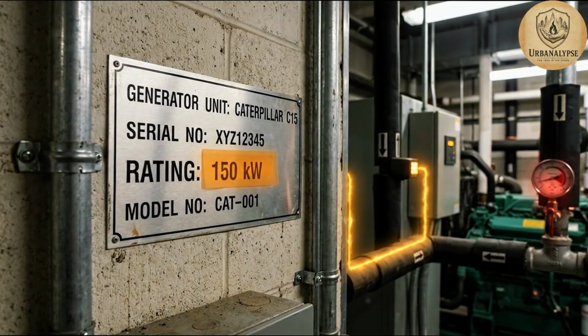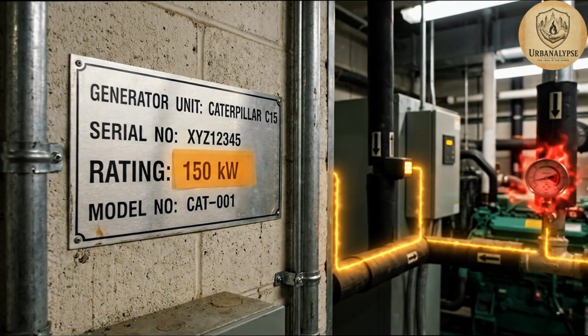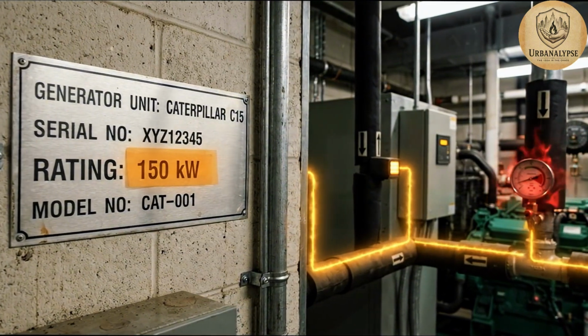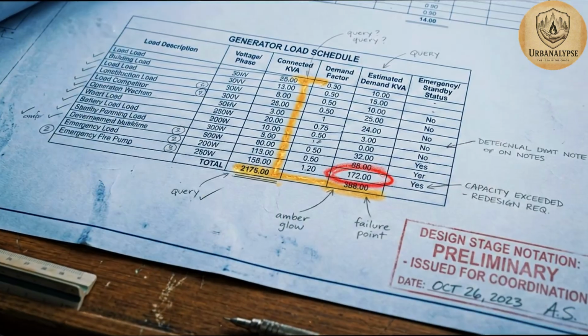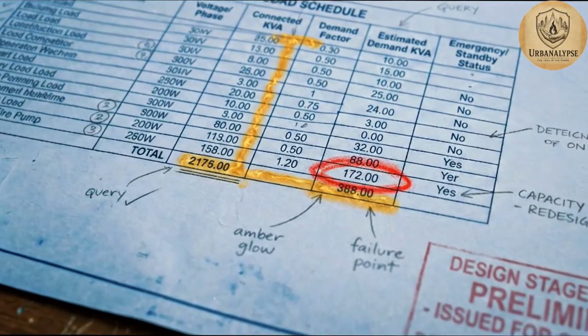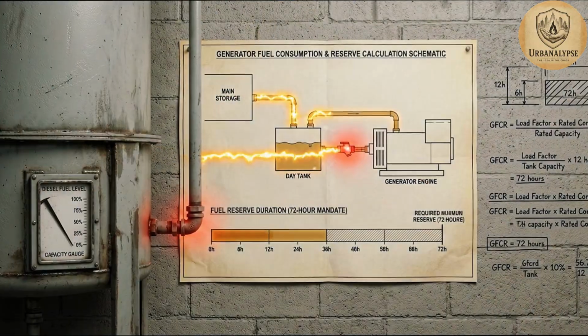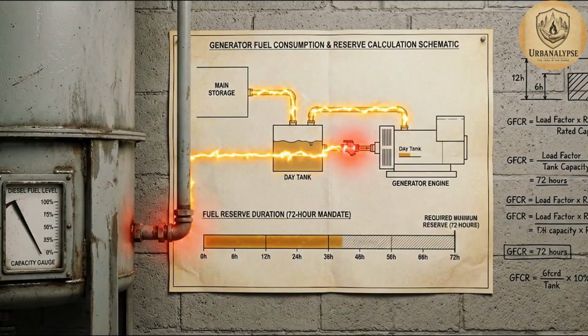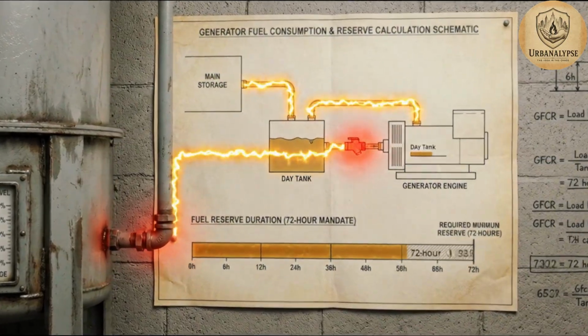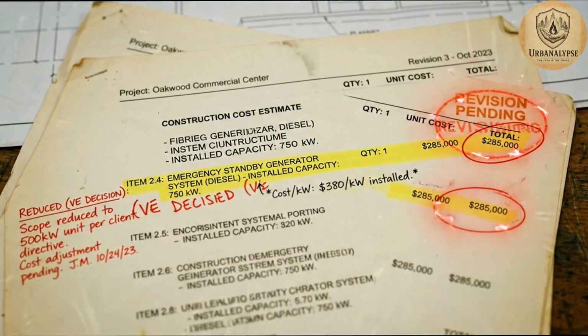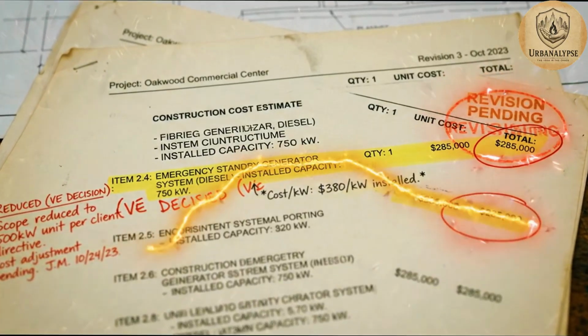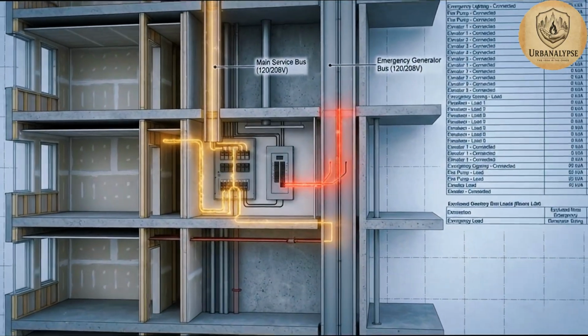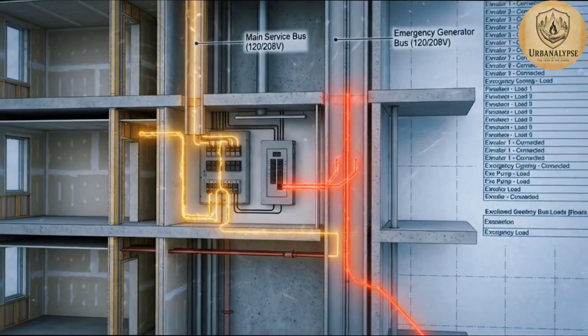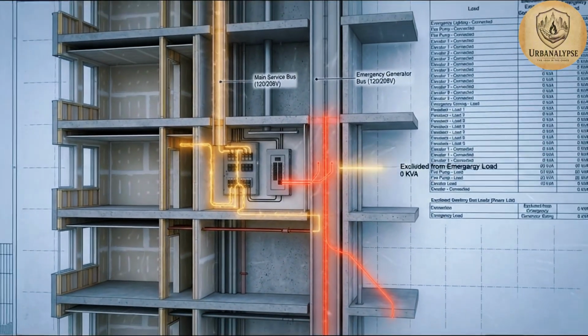Some buildings extend generator coverage to domestic water booster pumps as a legal option beyond the minimum code requirement. But that decision is made at the design stage, building by building, and most developers decline it to control installed generator capacity and fuel storage costs, both of which scale directly with contracted kilowatt output. Your unit was never budgeted into that emergency load calculation at any stage of the building's original electrical design.